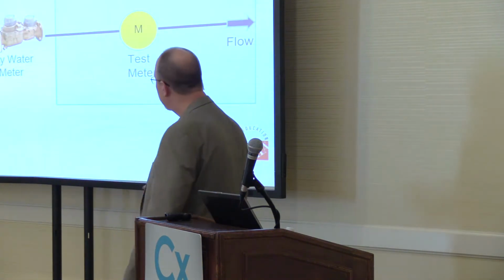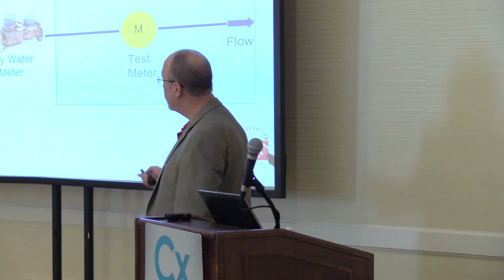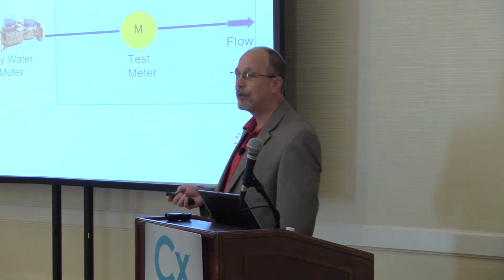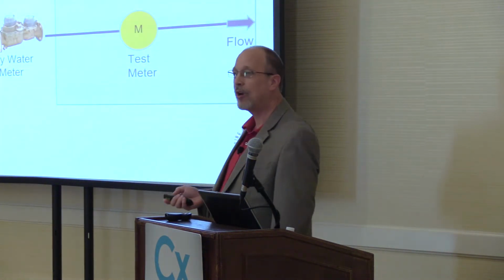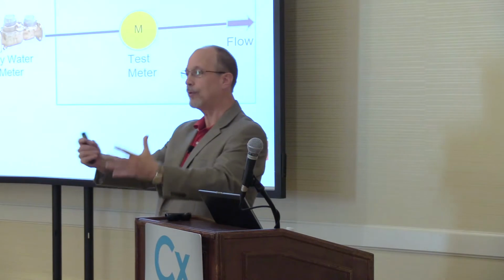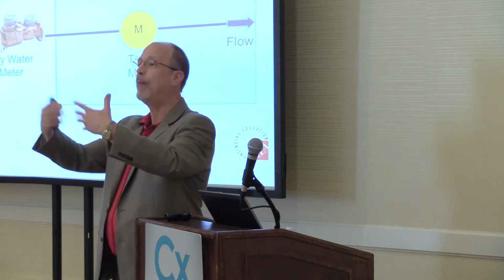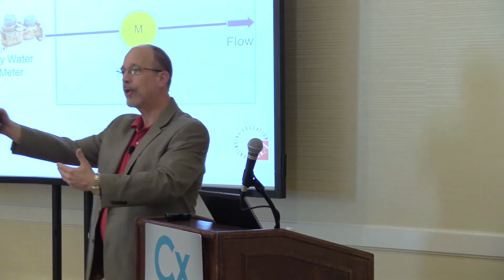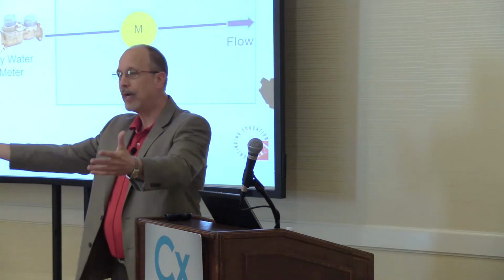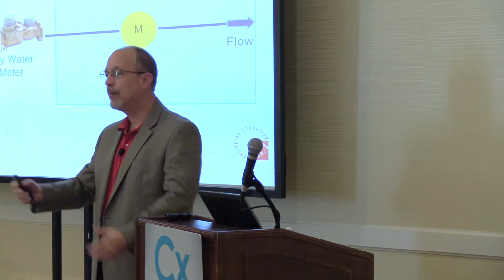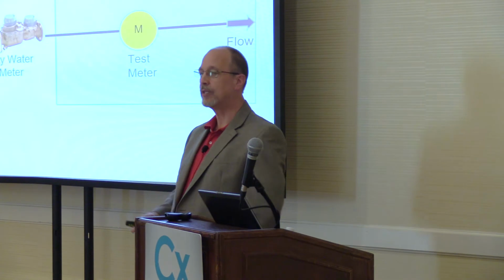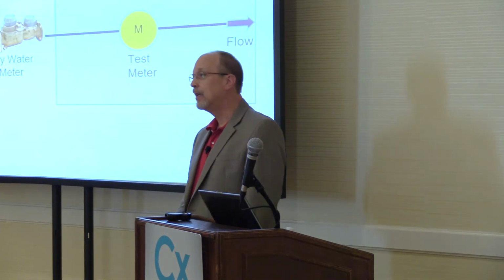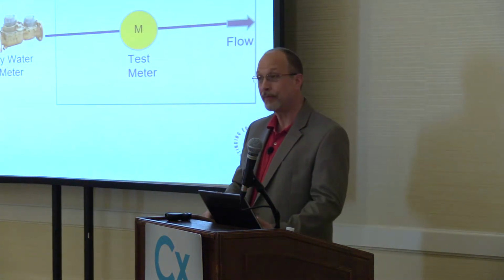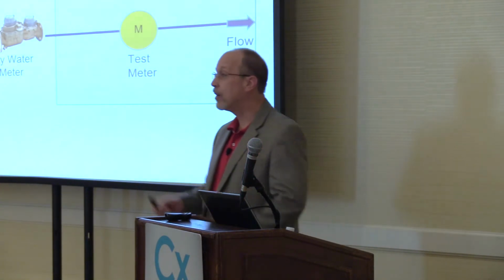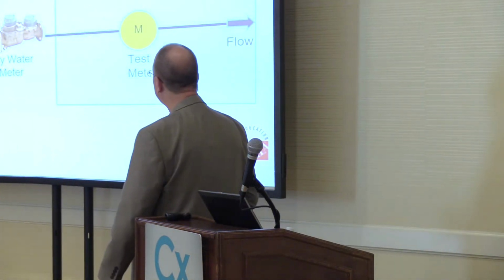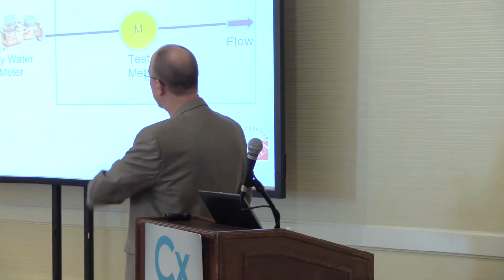So when you go to do the flow survey there, to check the city water meter, you better make sure that if it's a compound water meter, you have to say, I have an ultrasonic flow meter and it reads down to about 1/2 foot per second. You can calculate that out based upon whatever line size it is. And some brands you can go as low as 1/10 foot per second. But you're not going to see a toilet flush in a 10-inch pipe. So something to watch for. Every flow meter has a minimum flow rate, just like an ultrasonic flow meter.